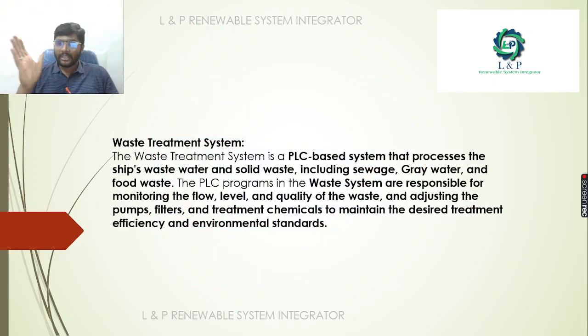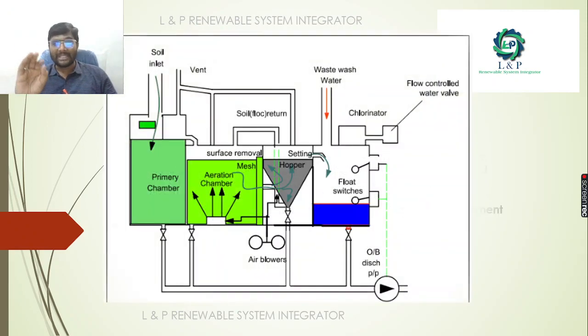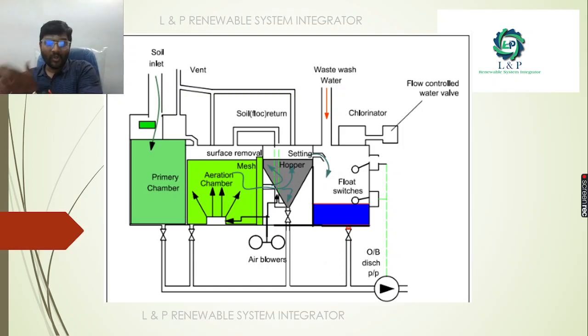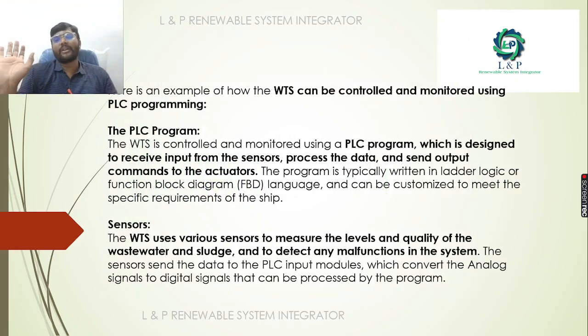Next, wastewater treatment. So in using the PLC, we process the ship's wastewater and solid waste, including the sewage, grey water and the food waste also. So wastewater system is responsible for monitoring the flow, level and quality of waste and adjust the pump, filters and treatment chemicals to maintain the desired treatment efficiency and environmental standards. This is how it looks like. We'll have a primary and we have an aeration chamber, we have hoppers and we have float switches also.